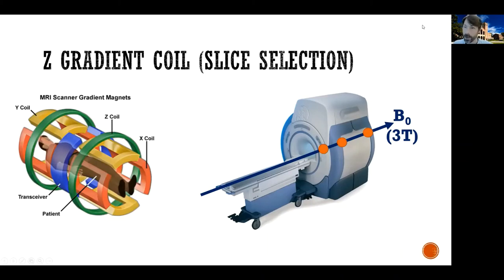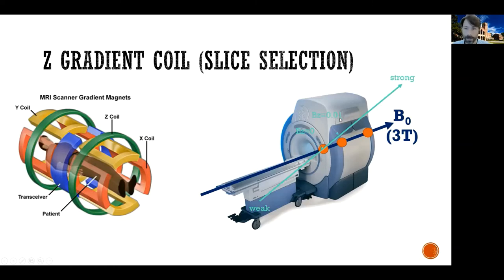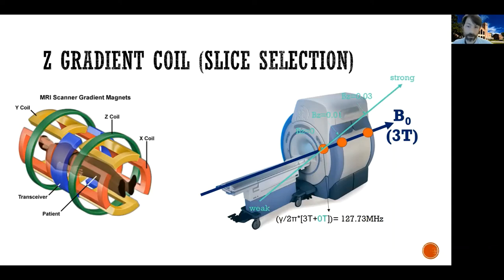The Z gradient coil creates a new magnetic field that might be weaker at one end — towards the feet — and stronger at the other end, towards the top of the head. Let's say this new field, which adds on top of B0, has a strength of zero here, 0.01 Tesla at the next point, and 0.03 Tesla further up — these numbers are made up, just to help with the example. So the first proton resonates at gyromagnetic constant over 2π times 3 Tesla plus 0, giving 127.73 megahertz.